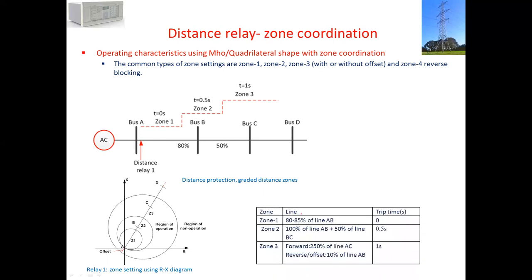This is a generic setting. Zone 1 is 85% of line AB with trip time of 0 second. Zone 2 is 100% of line AB plus 50% of line BC. Zone 3 is 250% of line AB, so 100% plus 50% plus another 100%, with trip time of 1 second. The offset is 10% of line AB, so 10% is extended behind the relay.